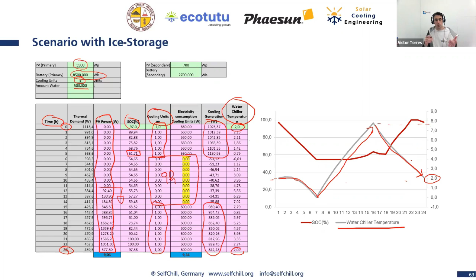This is providing us, at the end of the day, 2 different scenarios. So we can have a calculation, a design of a cold room without ice storage or with ice storage. Let's have a look here at the calculations. Without ice storage, we have 2.2 kilowatt peak for PV, and for the batteries, we need 21 kilowatt hour capacity. Yeah, these are the 1,700 amperes hour that we calculated. If we have ice storage, we can reduce the amount of batteries to 8.5 kilowatt hour, sorry, and we increase a little bit the PV.